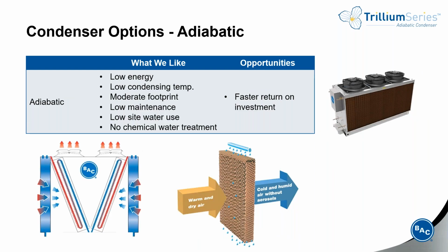Adiabatic products feature a dry coil and adiabatic media pads that are located outside of the coils. Water is distributed over the pads, and the fans pull ambient air across the pad media. This air is cooled as water evaporates off the pads and it's pulled across. This cooled air then reaches the dry coil for the heat exchange process to happen. This allows adiabatic products to be designed for condensing temperatures similar to evaporative products.